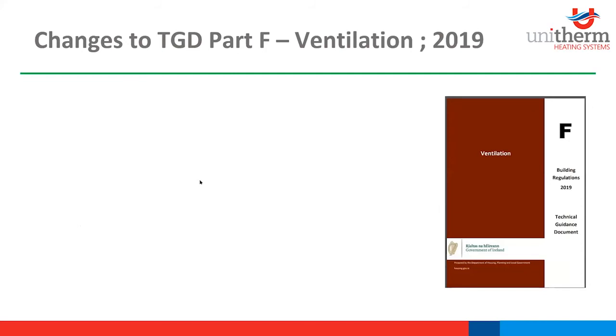A bit on TGD Part F, so Technical Guidance Document Part F on ventilation in dwellings. So natural ventilation is out the window due to the reduction in the air permeability backstop. This is brought down from 7 to 5 meters cubed per hour per meter squared. So this is making the new dwelling airtight basically. So ventilation is controlled mechanically now instead of conventional passive vents. Constant operation ensures removal of CO2 and volatile organic compounds for excellent indoor quality. So mechanical ventilation systems have to be designed, installed and commissioned by a competent designer and installer as per Part F 2019. And this obviously just came in there November 2020.